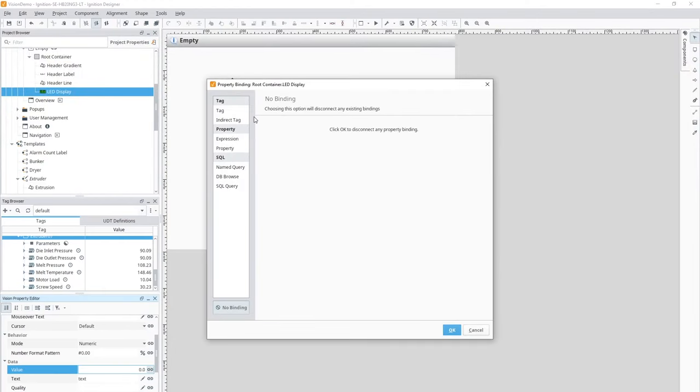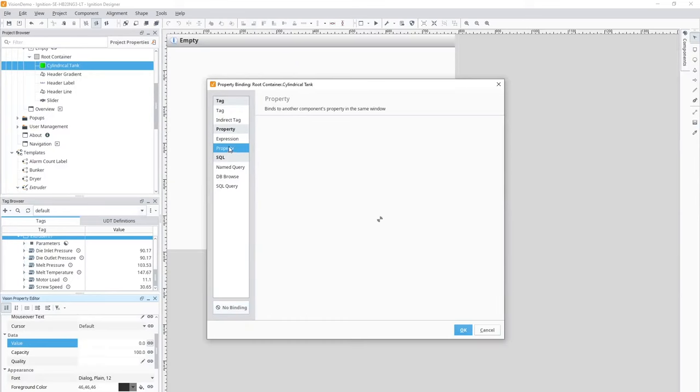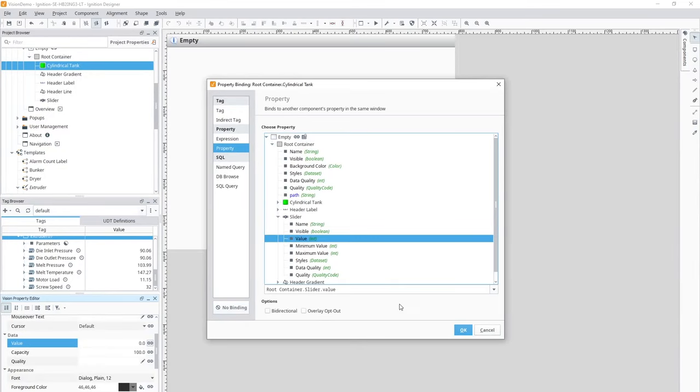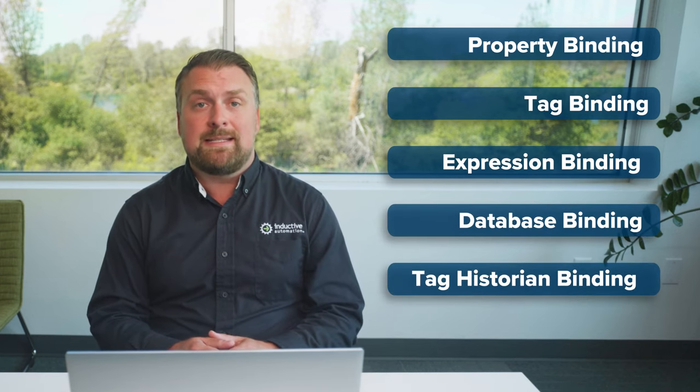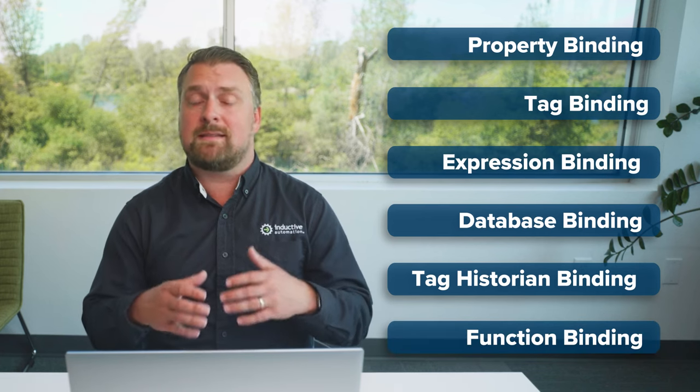Vision provides powerful binding functions to bring displays to life. A binding is a mechanism that allows a property on a component to change based on a change to a value elsewhere in Ignition. For example, the liquid level displayed in a tank graphic can be bound to the tag representing the liquid level in an actual tank. Vision supports six types of bindings: Properties to link to other properties on the screen; Tags, directly or indirectly linked to tags in Ignition; Expressions to link to calculations using Ignition's powerful expression language; Databases to link to SQL queries; Tag Historian to link to data from Ignition's tag historian module; and Functions to link to predefined functions such as getting alarm status and much more.